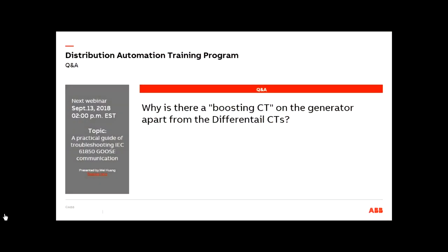Yes, I can. Perfect. So the first question that we received today is, why is there a boosting CT on the generator apart from the differential CTs? I guess I did not get the boosting CT part, but let me answer this question the way I understand it. The differential CTs are dedicated CTs, so you cannot have any other protection devices connected to that CT. So for a differential protection element, we need to have these dedicated CTs on both sides of the generator.